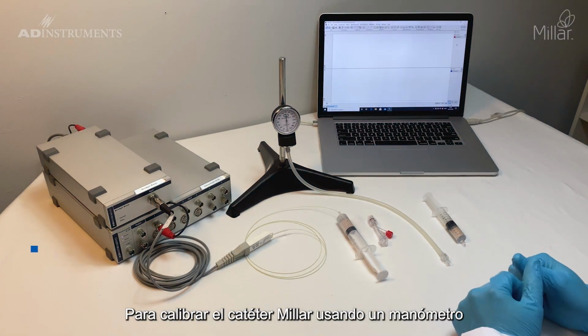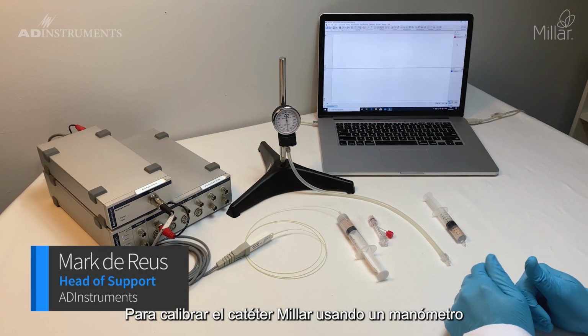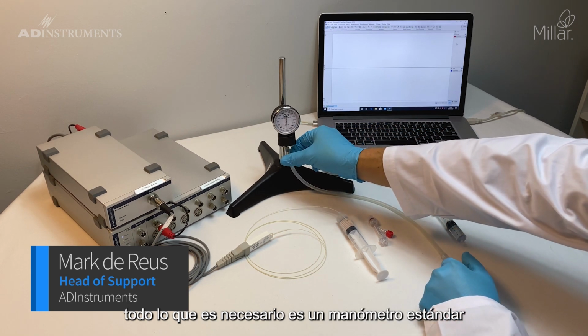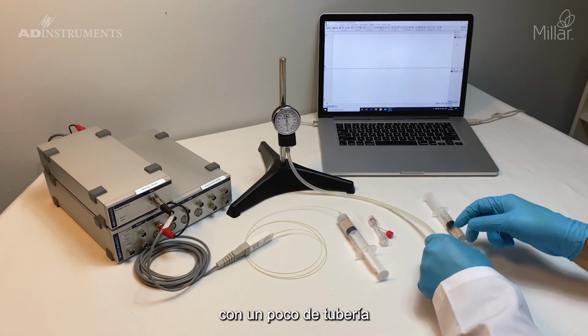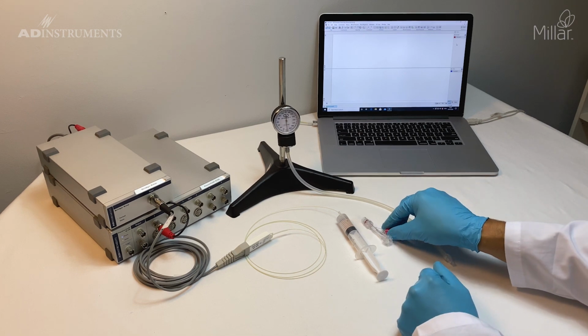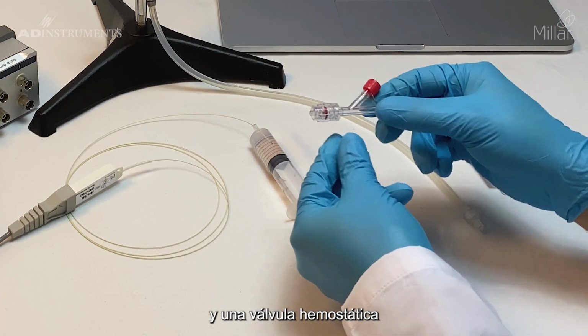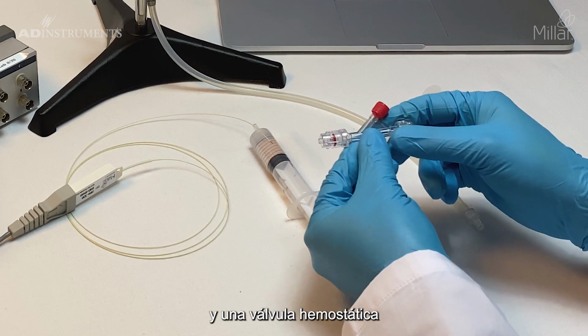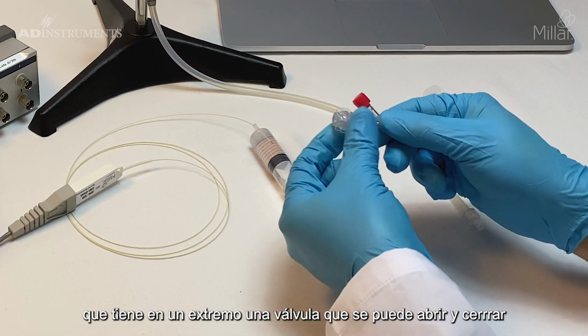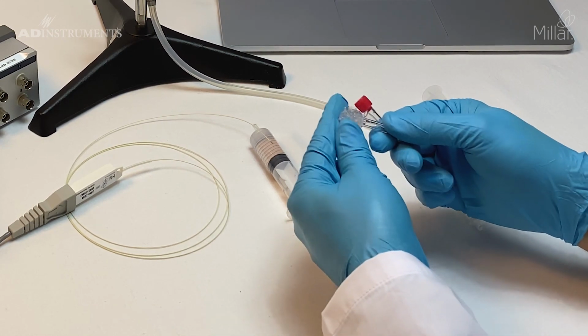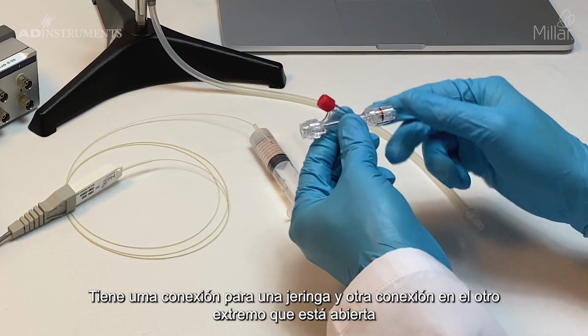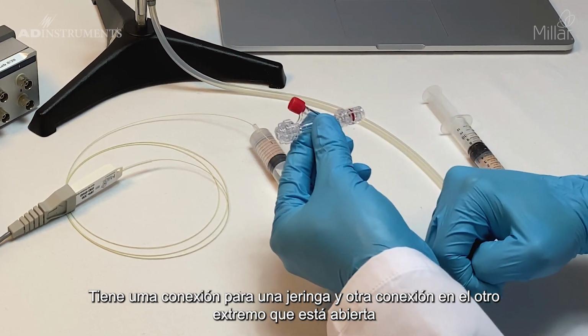To calibrate the Millar catheter using a manometer, all I need is a standard manometer with some tubing and a hemostatic valve. One end has got a valve which you can open and close. It's got a port for a syringe and then another connector on the other end which is open.